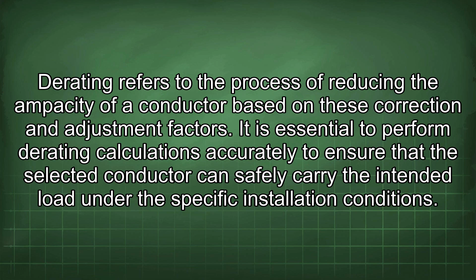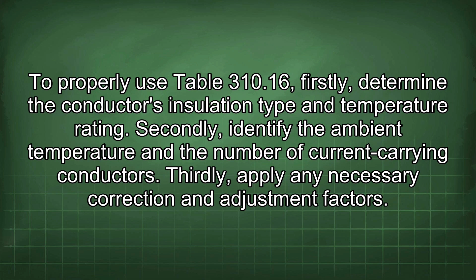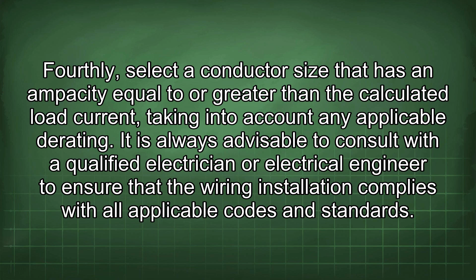To properly use Table 310.16, firstly, determine the conductor's insulation type and temperature rating. Secondly, identify the ambient temperature and the number of current-carrying conductors. Thirdly, apply any necessary correction and adjustment factors. Fourthly, select a conductor size that has an ampacity equal to or greater than the calculated load current, taking into account any applicable derating. It is always advisable to consult with a qualified electrician or electrical engineer to ensure that the wiring installation complies with all applicable codes and standards. Improperly sized conductors can lead to overheating, insulation damage, and potentially dangerous electrical hazards.